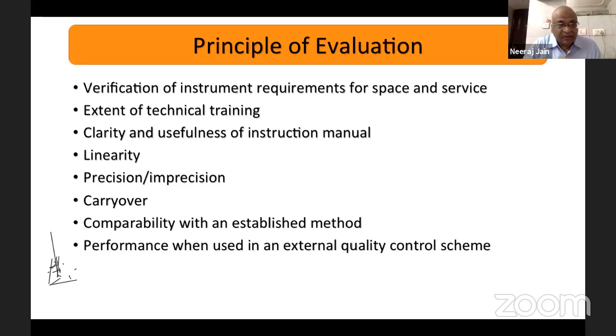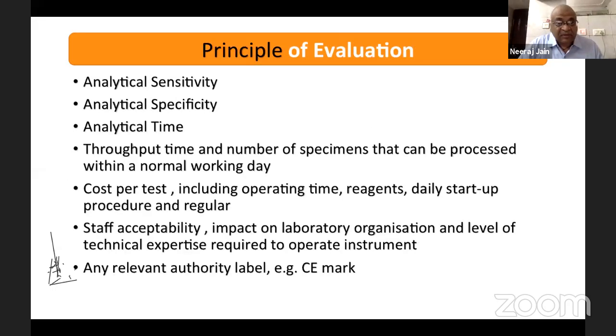Linearity means the maximum value which you can report without dilution. Also check precision for various analytes. Carryover means a low value sample is affected by a previously run high value sample. Check that also. Compare your result with the established method. See performance in aqueous samples also. Analytical sensitivity means what is the minimum difference that the machine or method can detect.